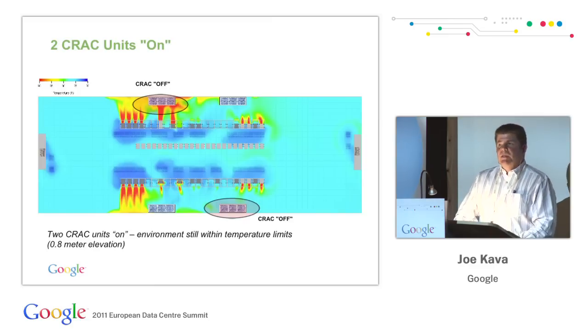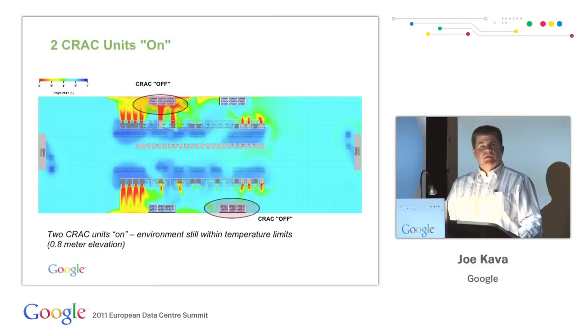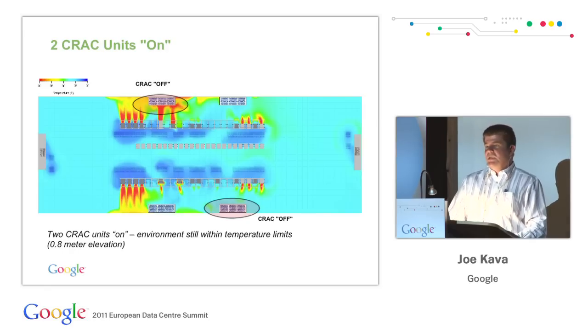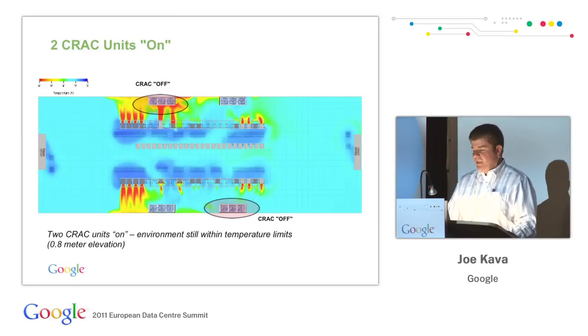We also, I mentioned that we turned down unneeded CRACs. In this case, this shows what the temperature profile looks like in the cold aisle with only 2 of the CRACs running. On this picture, the upper left-hand and the lower right-hand CRAC units are turned off. Because we had very modest load at this time in this room, we still had totally sufficient cooling. In the cold aisle, we were maintaining our temperature set points well. We didn't have any hot spots in the cold aisle, and so we were able to completely operate in this condition.